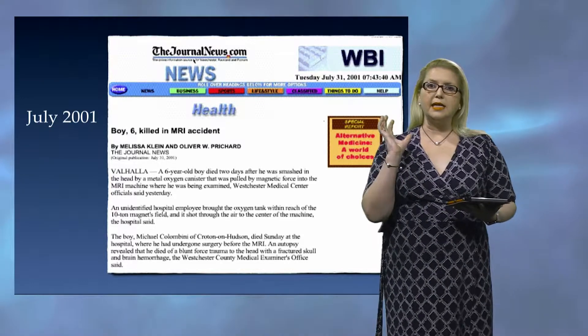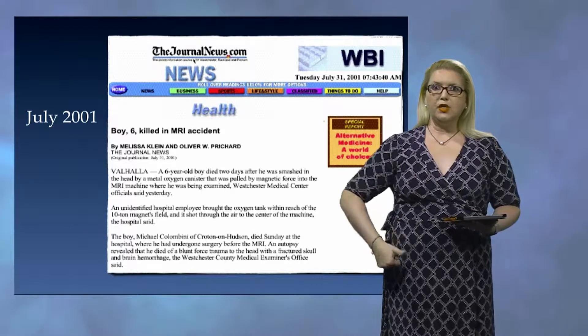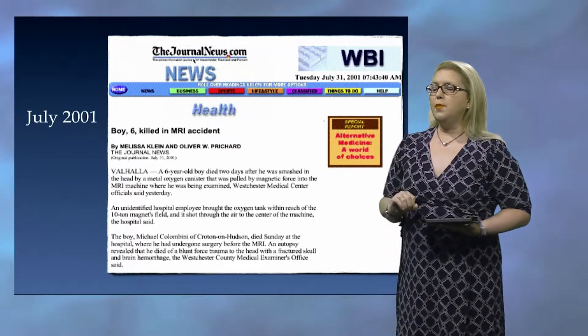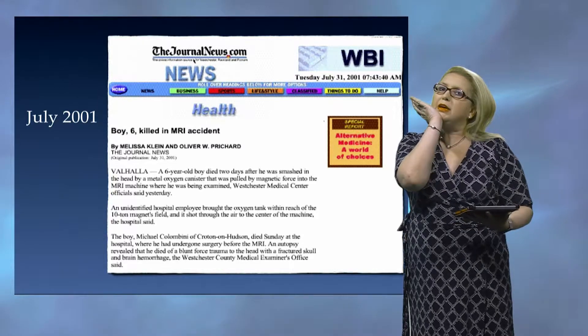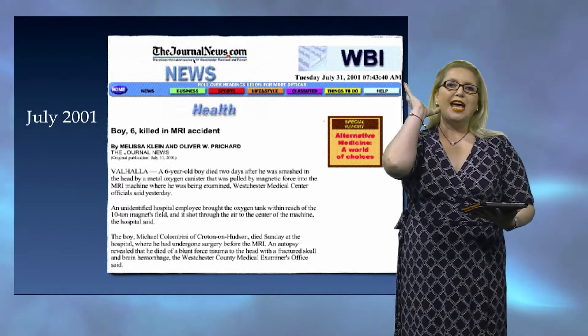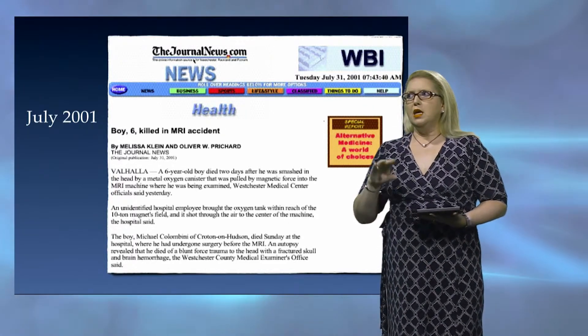Michael Colombini's head was right where you actually enter the bore, and that's where the translational force is the strongest. So what ended up happening is the oxygen tank was rapidly pulled from her, and it hit Michael in the head, and it became lodged between his head and the head coil, where he would be entered into the magnet.